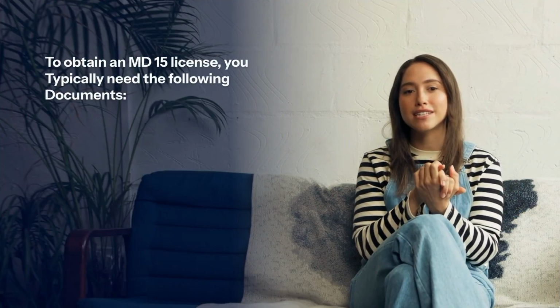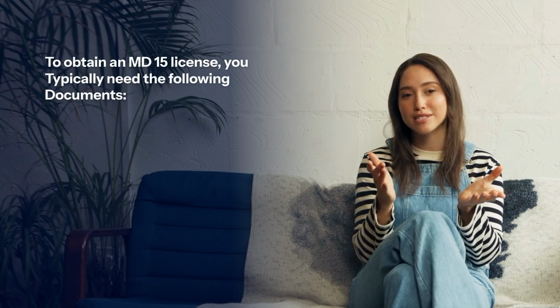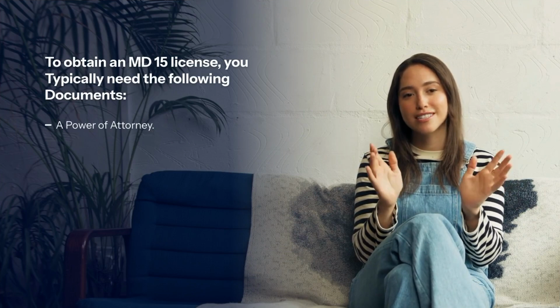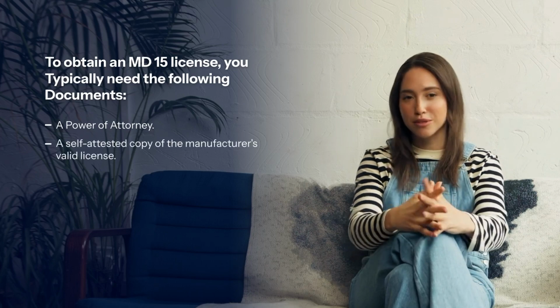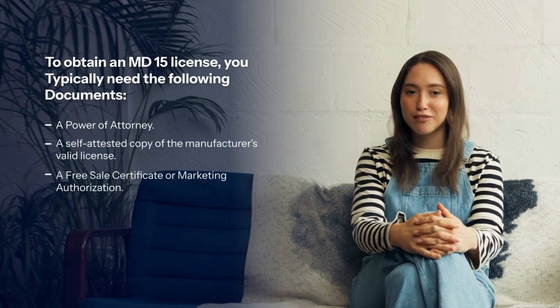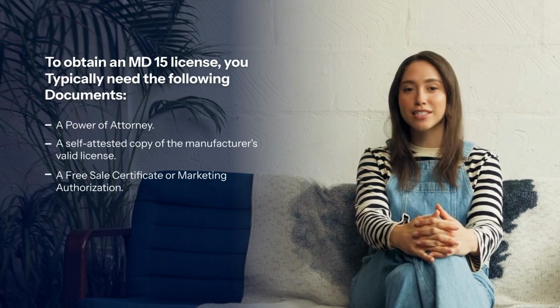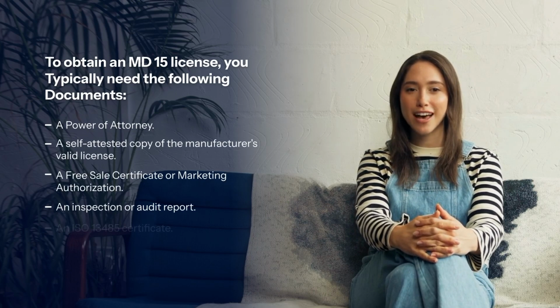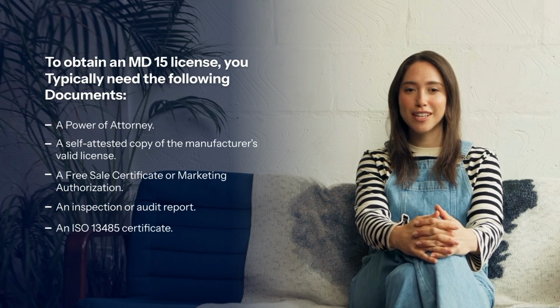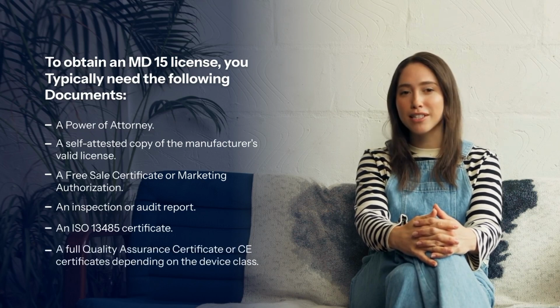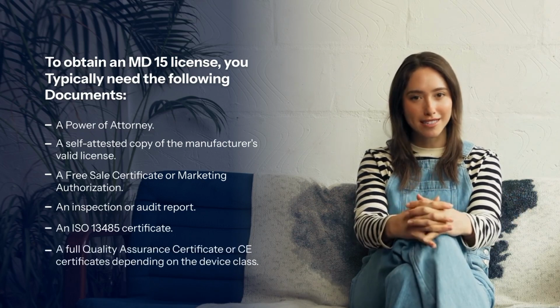Now let's talk about the documentation. To obtain an MD-15 license, you typically need the following documents: a power of attorney, a self-attested copy of the manufacturer's valid license, a free sale certificate or marketing authorization, an inspection or audit report, an ISO 13485 certificate, a full quality assurance certificate or CE certificates depending on the device class.